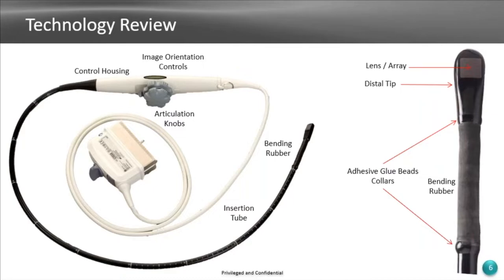And I was talking about adhesives. I want to stop for a minute—this isn't part of the presentation—but when you think about adhesives, there's thousands and thousands of different adhesives out there. So what adhesive do you use when you replace these glue beads and locking collars? The answer is, I don't know, what does the OEM use? And the OEM doesn't tell us. So the way we go about these things is we try to determine what the OEM used, and then we take samples of that adhesive we believe is proper and test it for compatibility with every cleaner and disinfectant that OEM recommends for that device.